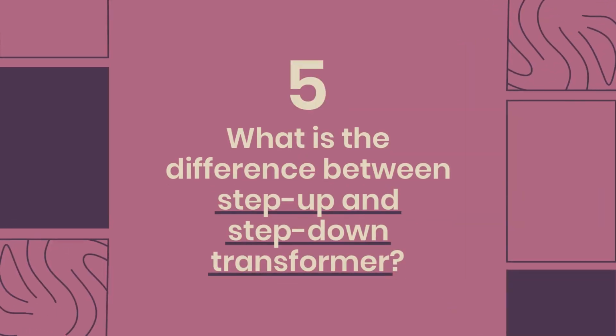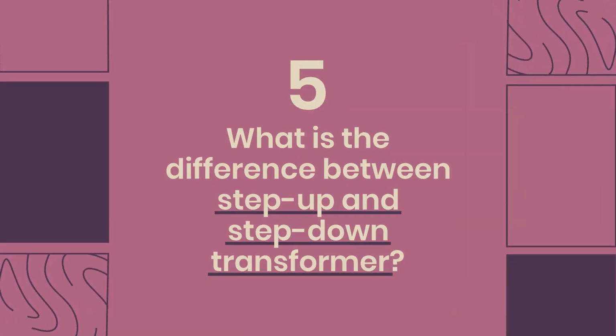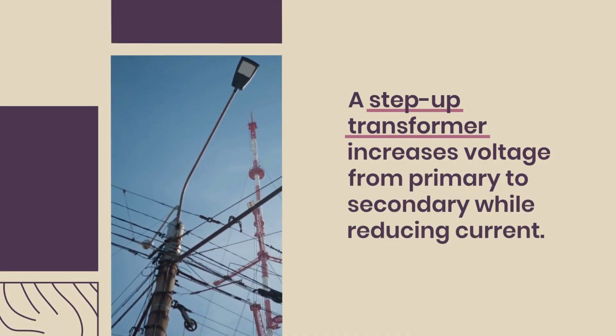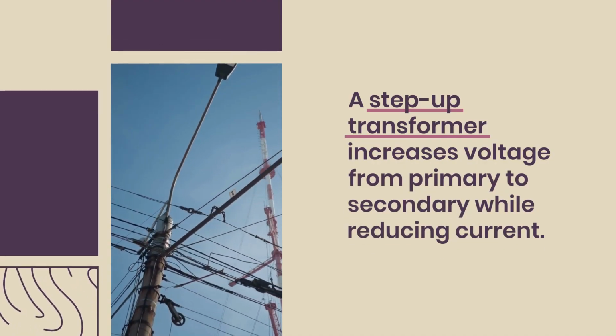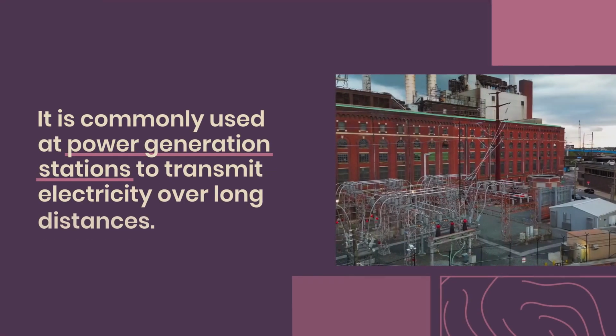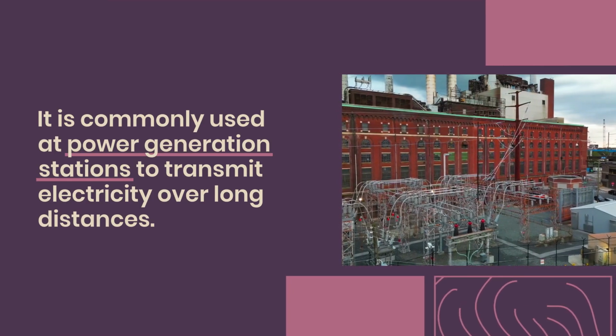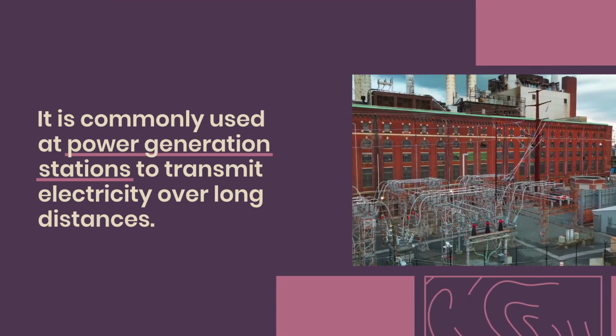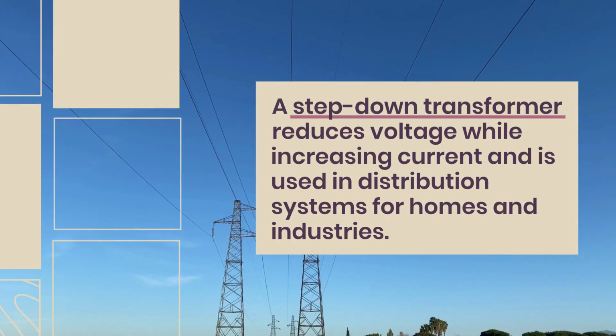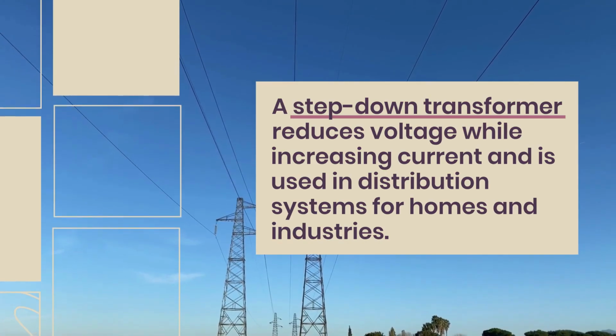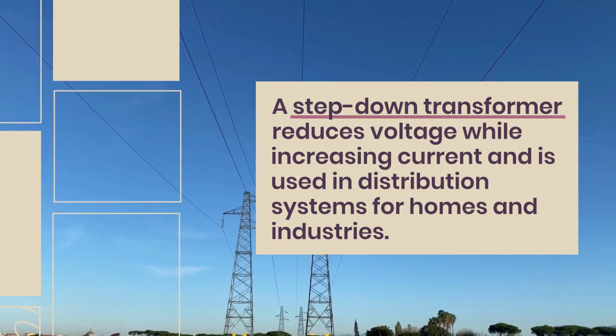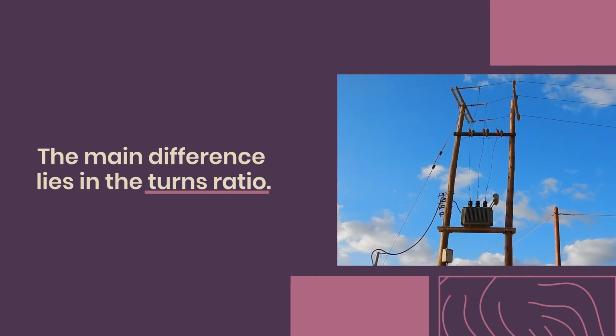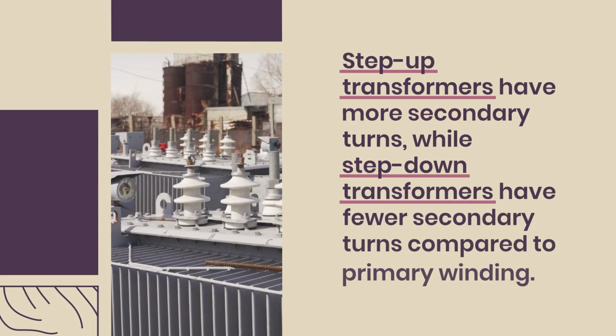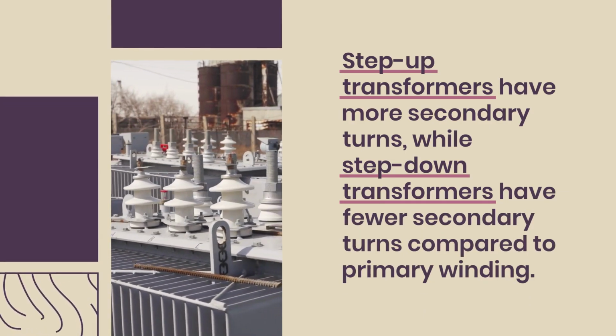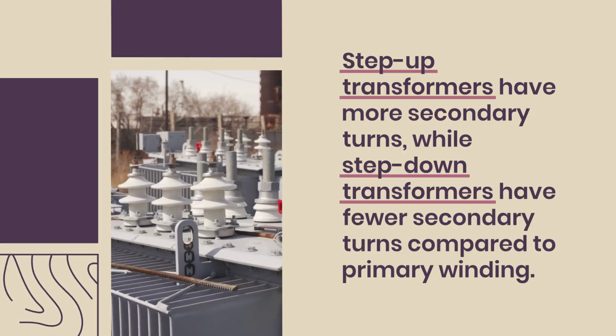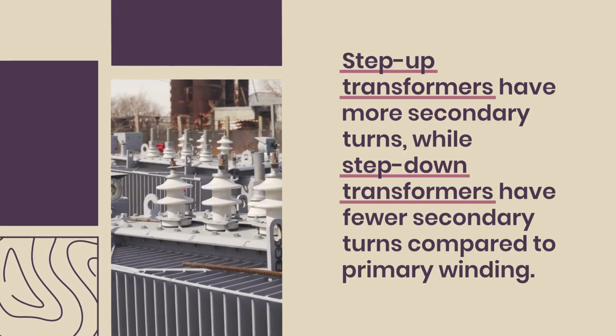5. What is the difference between step-up and step-down transformer? A step-up transformer increases voltage from primary to secondary while reducing current. It is commonly used at power generation stations to transmit electricity over long distances. A step-down transformer reduces voltage while increasing current and is used in distribution systems for homes and industries. The main difference lies in the turns ratio. Step-up transformers have more secondary turns, while step-down transformers have fewer secondary turns compared to primary winding.